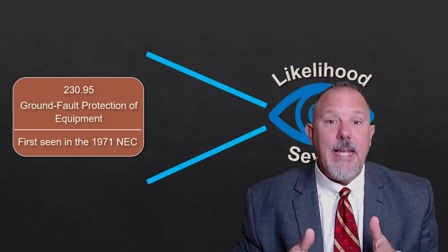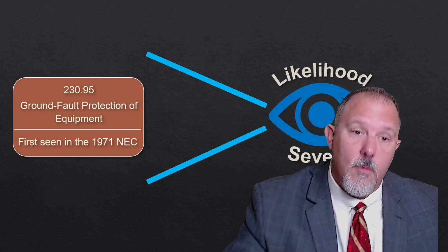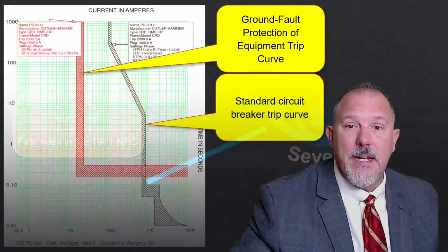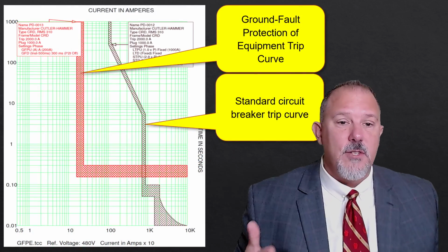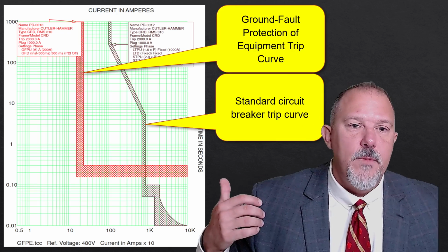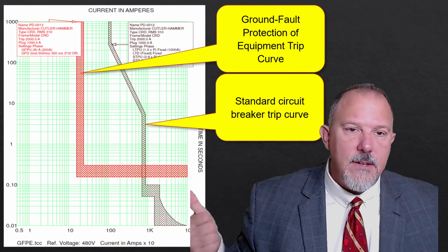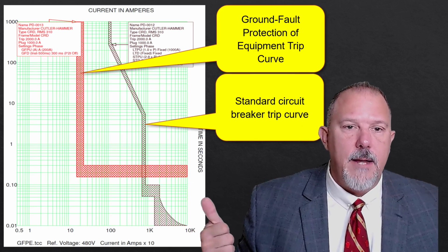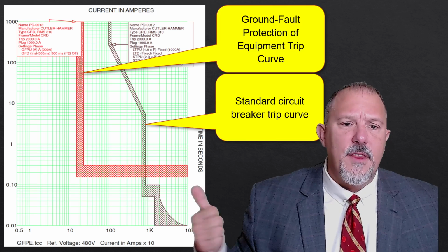230.95 GFPE. We talked about this earlier already, first seen in the '71 code, but here are the TCC curves. This is what it does. This is a 2,000 amp circuit breaker with a 1,000 amp plug. So this is at 1,000 amps.